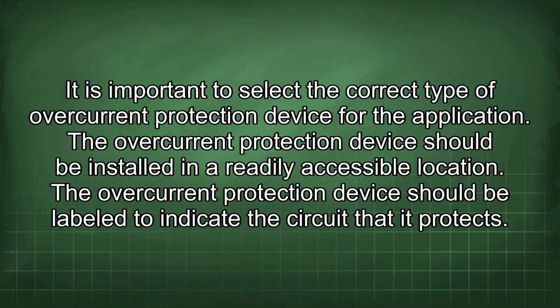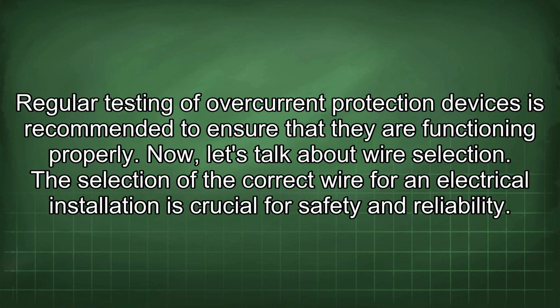It is important to select the correct type of overcurrent protection device for the application. The overcurrent protection device should be installed in a readily accessible location. The overcurrent protection device should be labeled to indicate the circuit that it protects. Regular testing of overcurrent protection devices is recommended to ensure that they are functioning properly. Now let's talk about wire selection. The selection of the correct wire for an electrical installation is crucial for safety and reliability.